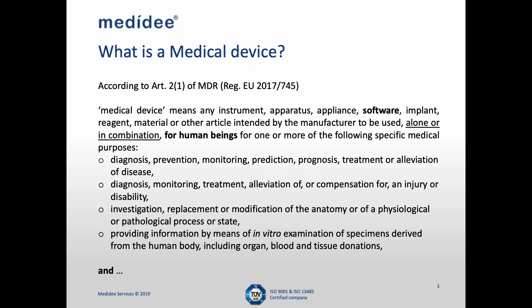And the second one is, after defining that the product addresses human beings and specific medical purposes, we need to establish or justify that the principal intended action is not achieved by pharmacological, immunological, or metabolic means in or on the human body, but that it can be assisted by such means. So the device intended for use on human beings to address a particular medical condition or medical function must not have its principal mode of action by pharmacological, immunological, or metabolic means. Rather, these actions can be part of its secondary mode of action, but the principal action is still going to be the mechanical way.